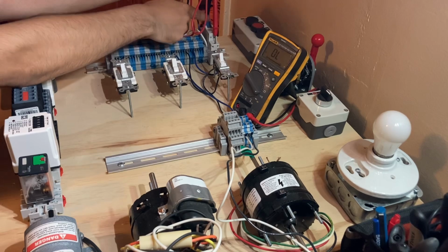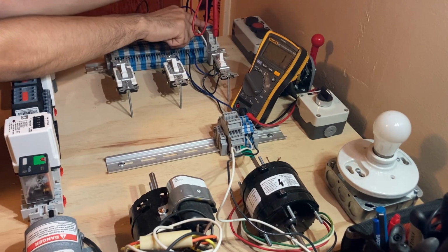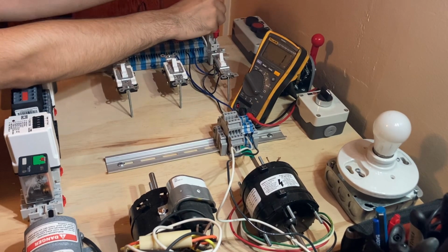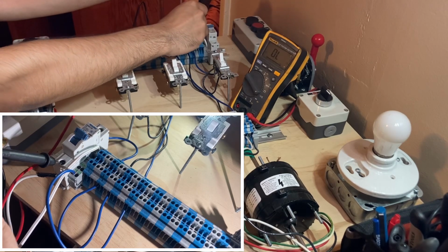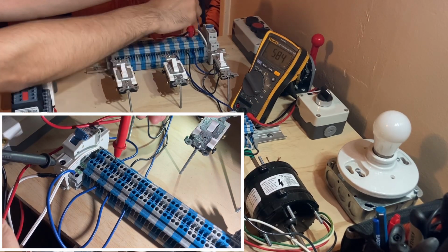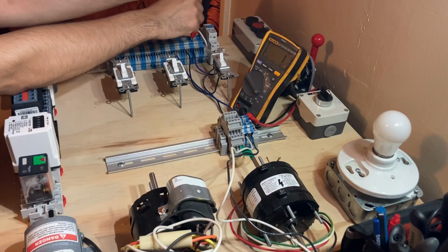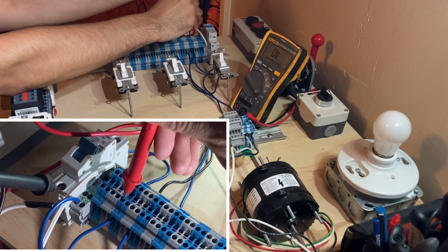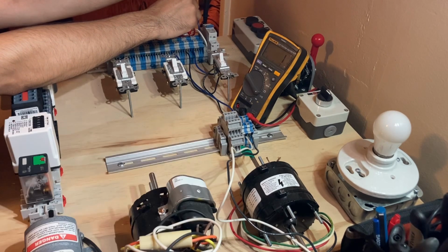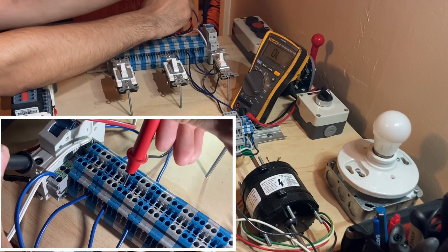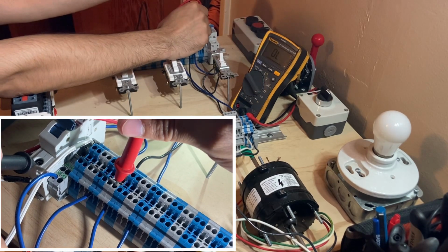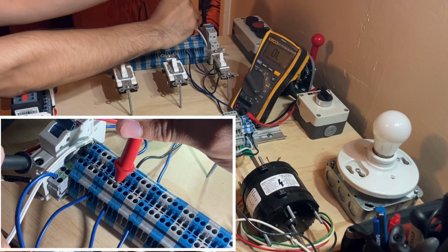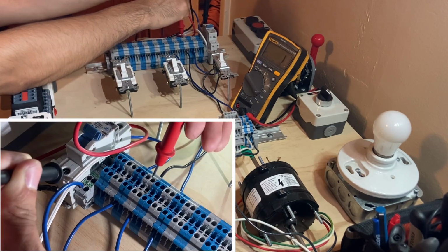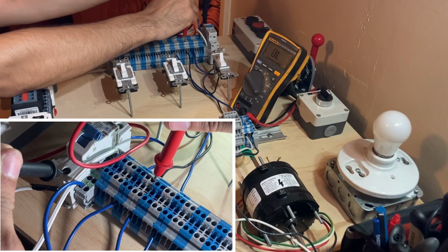Now as we turn our circuit breaker on and off, we could see that we have continuity there. It goes from open line to 1, meaning that every time we turn our breaker on, we have a connection. Now we're following the terminal blocks. Have continuity all the way.